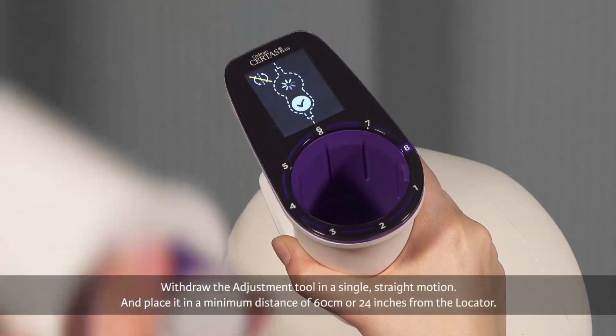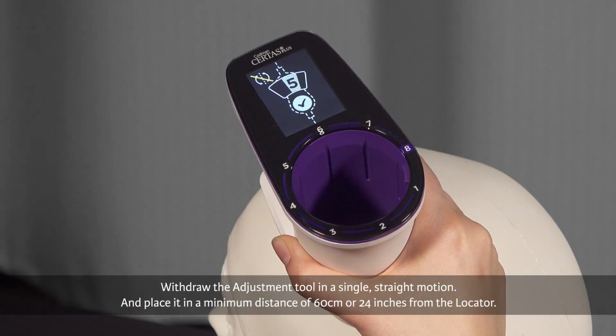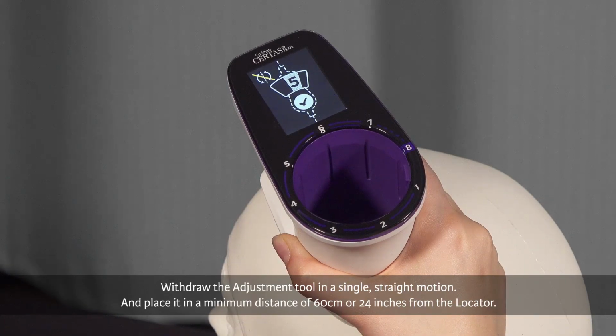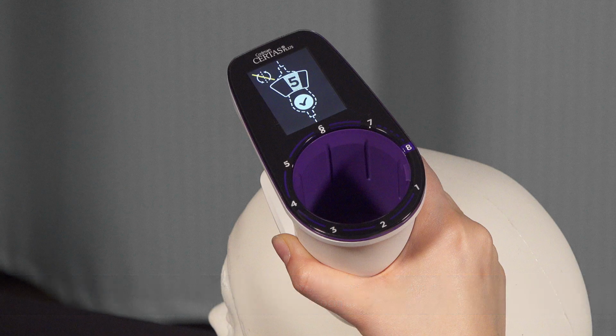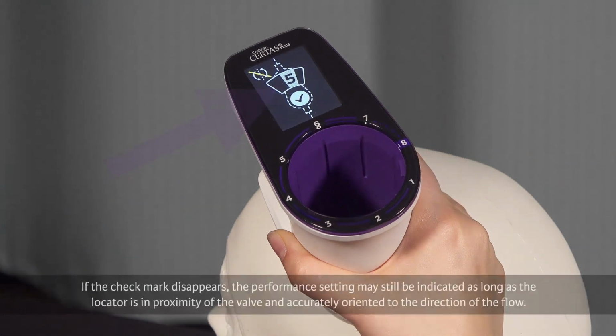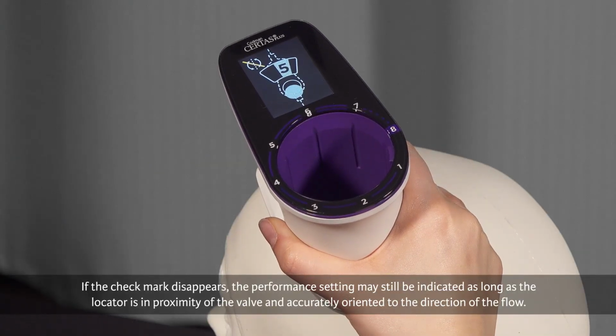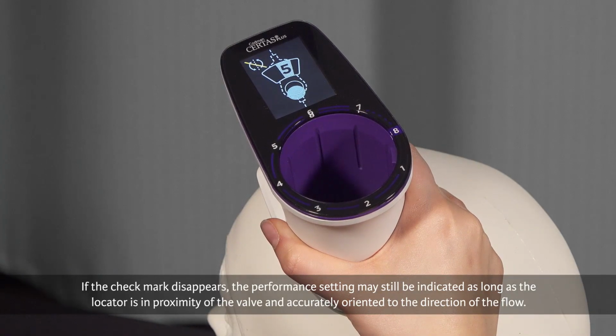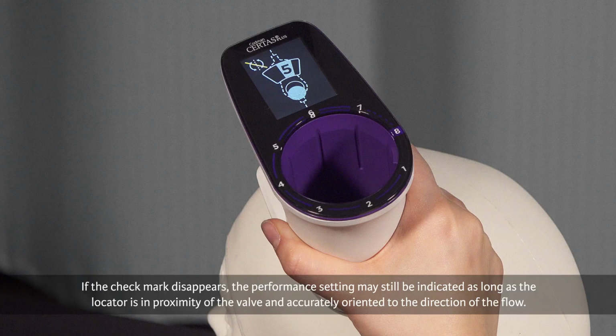Withdraw the adjustment tool in a single straight motion and place it in a minimum distance of 60 centimeters or 24 inches from the locator. Confirm the number in the window matches the desired performance setting of the valve. If the check mark disappears, the performance setting may still be indicated, as long as the locator is in proximity of the valve and accurately oriented to the direction of flow.